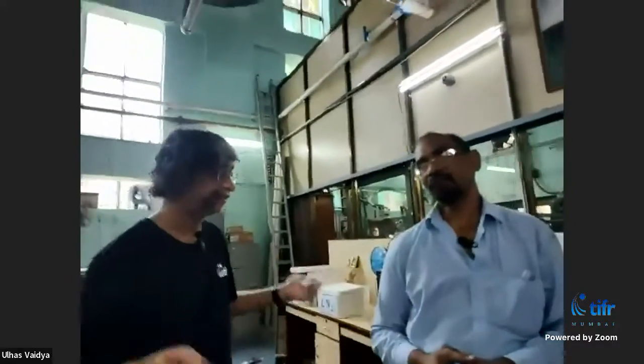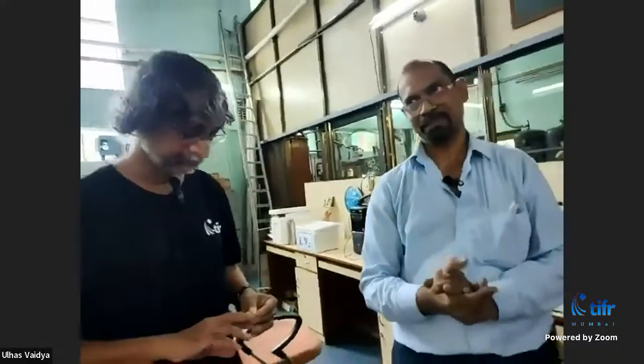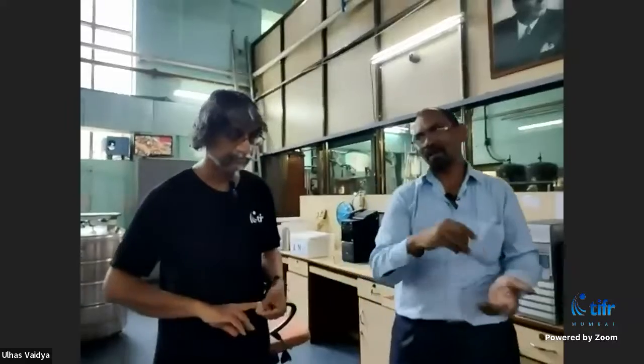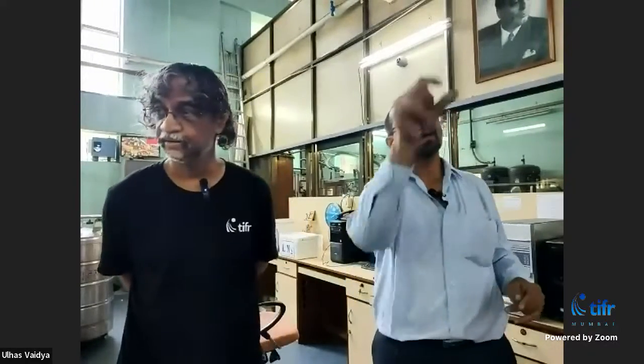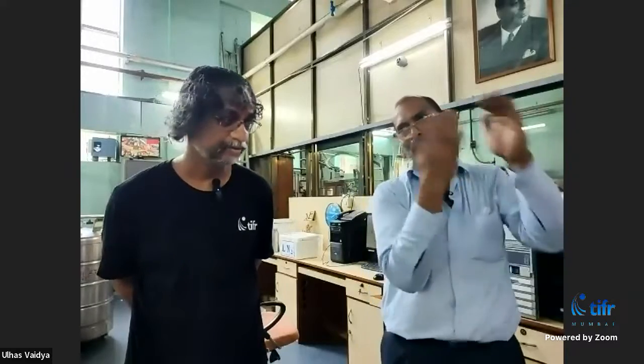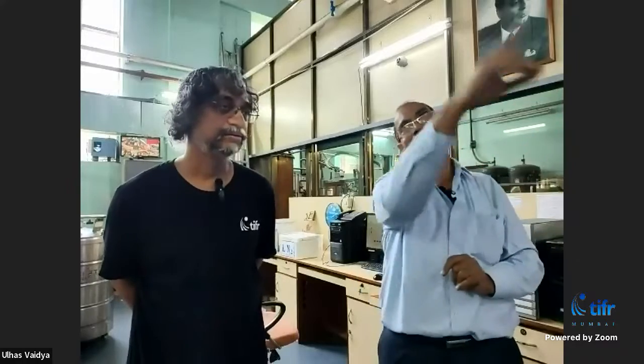We recover about 85% of the gas. Liquefaction of 1 liter of helium needs 800 liters of gas - so 1 liter of liquid helium evaporating creates 800 liters of gas. So every transfer to the system, the gas heats up everywhere, and that gas is collected in the recovery system. It's pretty good that we can recover 85% of the helium.